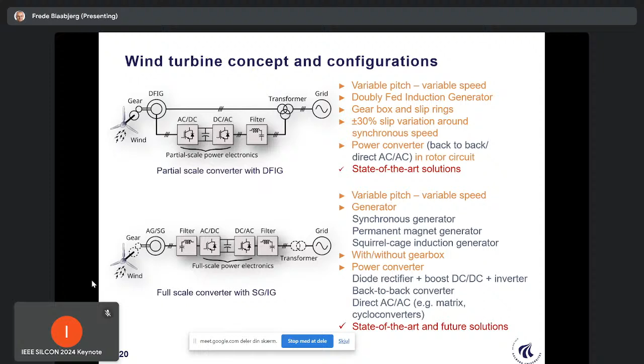But the disadvantage, seen from a control perspective, is that when something happens on the grid, we will also see it directly on the stator of the generator. With the full-scale configuration, if something happens at the grid, we can decouple the two systems so the generator doesn't see it, and if something happens at the generator, the grid doesn't see it. That is of course easier to handle for the whole wind turbine. But on the other hand, the power level of the power electronics and the power conversion has to be handled at full scale, twice over.